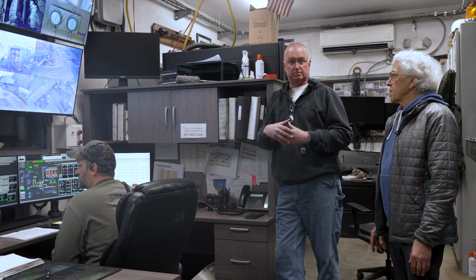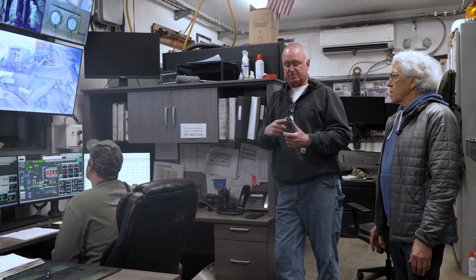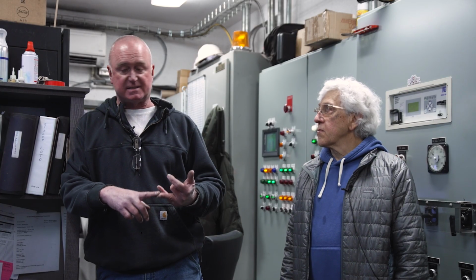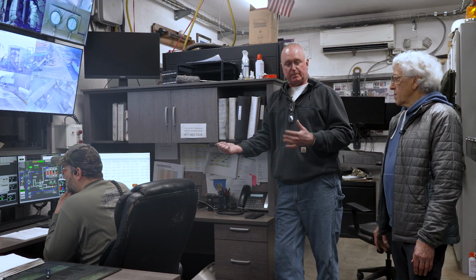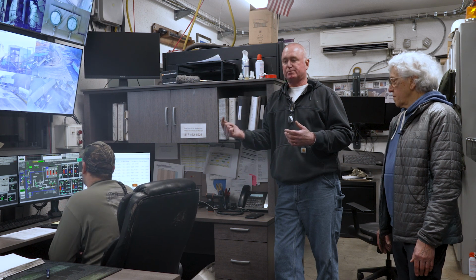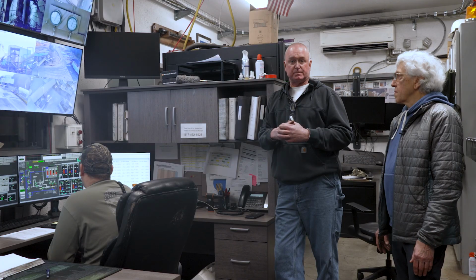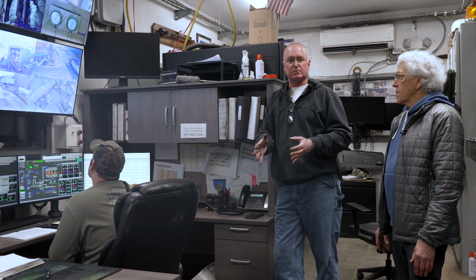Once the boiler is full, we fill what's called a deaerator, a DA tank, which deaerates, stores, and preheats the feed water. So we want to make the boiler fire as economically as possible, so we use as little fuel as possible. That's why we talked about preheating the feed water in the economizer with flue gas with the latent heat. That's why we talked about preheating the combustion air with flue gas. That's latent heat. Everything to make things more efficient. Once we store enough water, deaerate, and preheat it, the water then goes to feed pumps, which pump the water into the boiler steam drum.